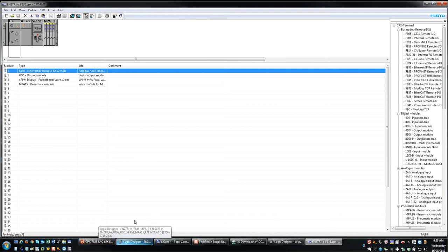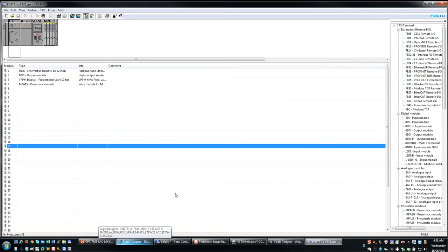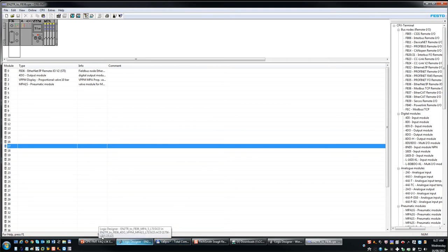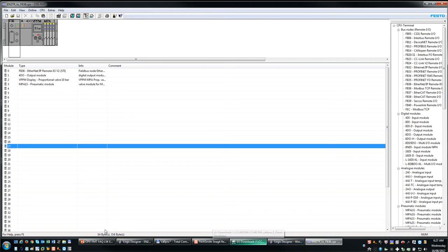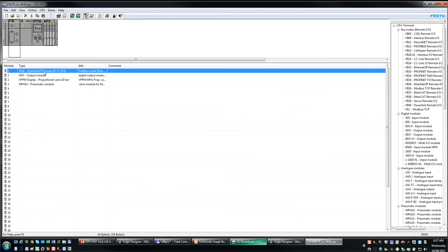And the Rockwell software does not allow an import of zero bytes of input. So if your manifold is only valves, for example, then the FB36 has a couple dip switches that will activate diagnostics.